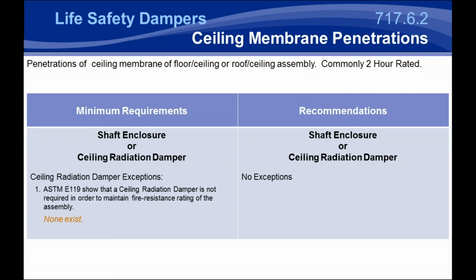Now, we do get calls about what type of assembly or what type of damper is needed per assembly. At that point, we always ask the question, what floor ceiling or roof ceiling assembly are you using, to make sure that you can have penetrations? The first type that does allow penetrations is a generic floor ceiling or roof ceiling assembly. Typically, most of these are drop ceilings, where you're using fire-rated acoustical panels protecting corrugated steel above, and then either some type of fiberboard, ceramic board, or poured concrete.